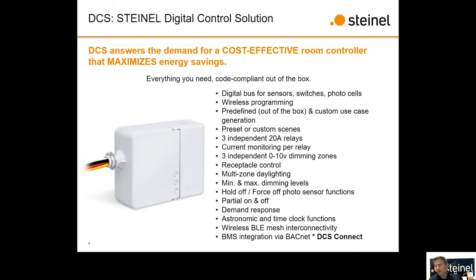We've also got wireless BLE mesh. So BLE mesh allows us to connect multiple devices. So if you've got a scenario where you have more than 3 relays, more than 3 circuits, if you want to go 6, you can connect 2 devices together, and you can combine those relays into a single switch load, for example. We like to think of it as enabling the kill button. So you can have one wall station at the back door of a facility that can span across all the digital controllers on the property and turn off all the lights at once with one hit of one button. So one switch connected to all the relays across all the DCSs.